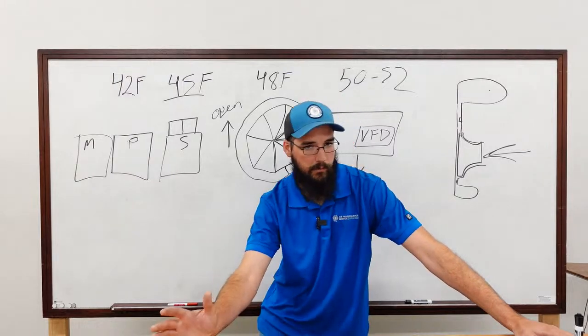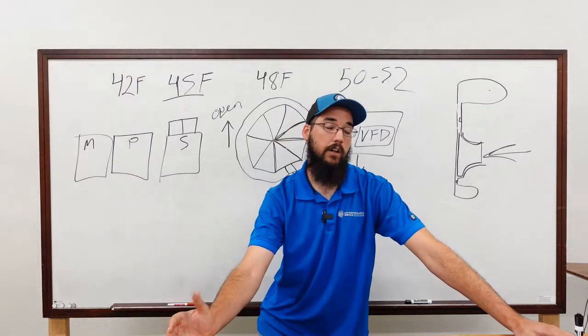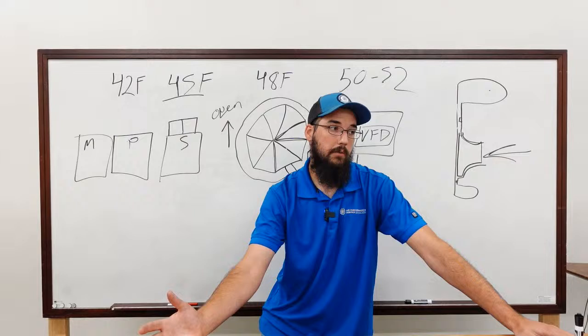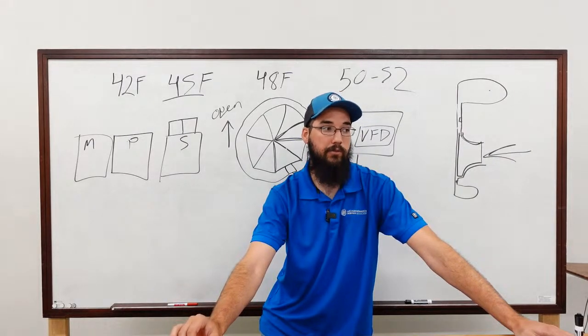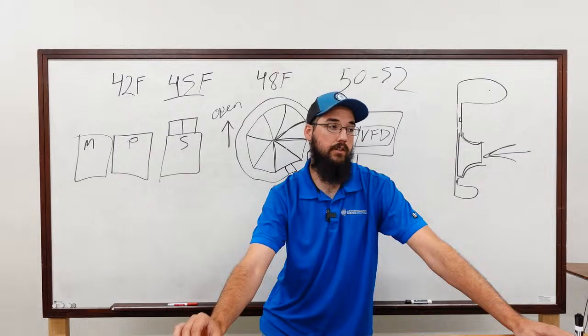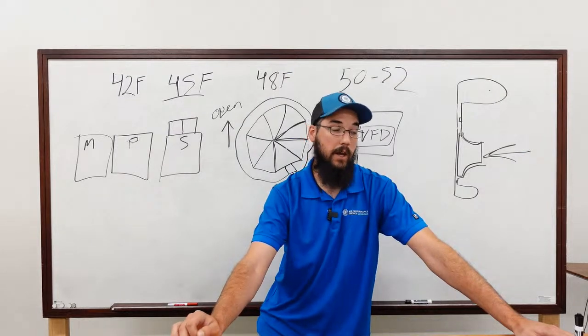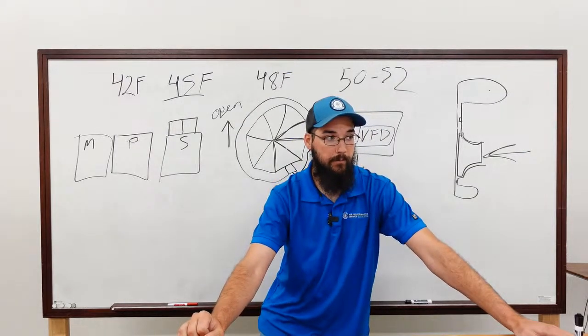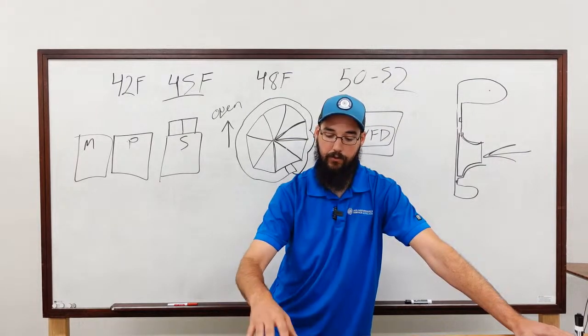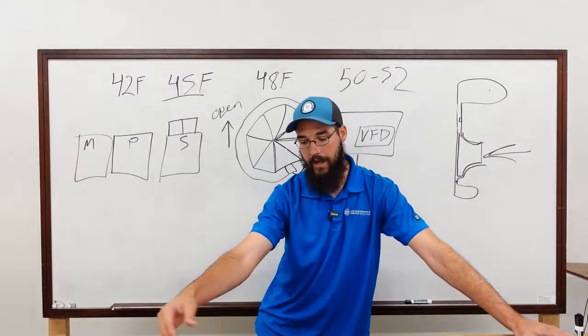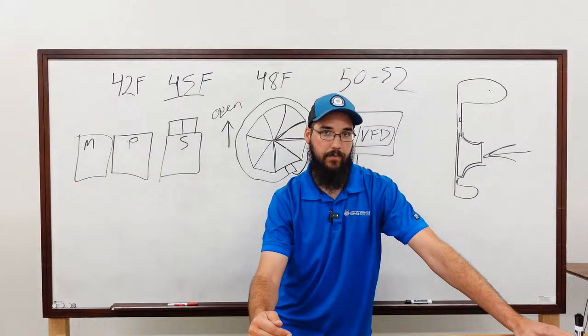Because remember from yesterday, the condenser, unless it has a subcooler circuit, most of the time may not have liquid refrigerant standing high enough to touch the tubes, but the evaporator absolutely will.